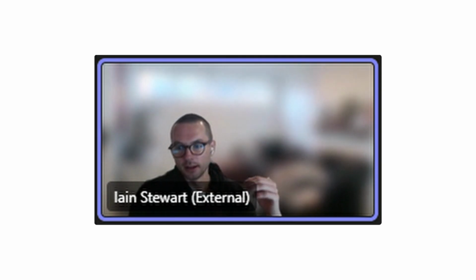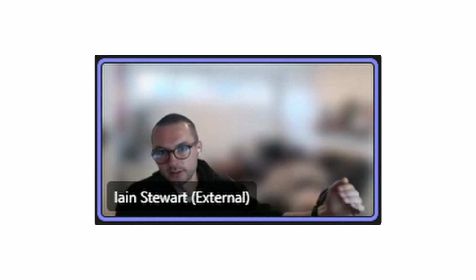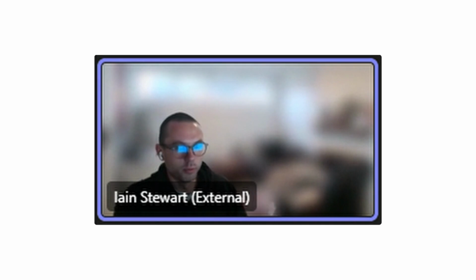So if we get into some territory where we're actually supplying too much chilled water to the chiller, we can have a low delta T. So the return temperature to the chiller might be 7.5 degrees Celsius and the leaving temperature is 6 degrees. In an ideal world, we'd want to reduce that flow to get that up around 12 degrees return and 6 degrees leaving so that we've got a higher delta T across the chiller. Savings there then comes twofold, really.